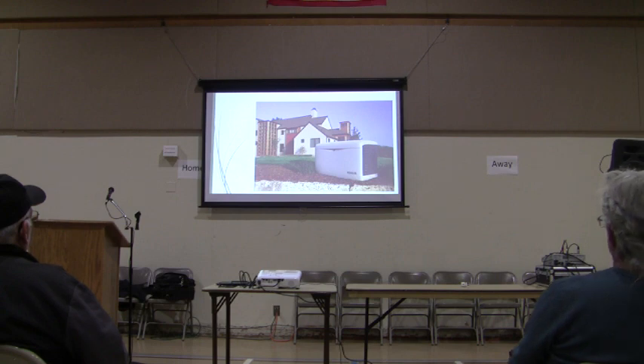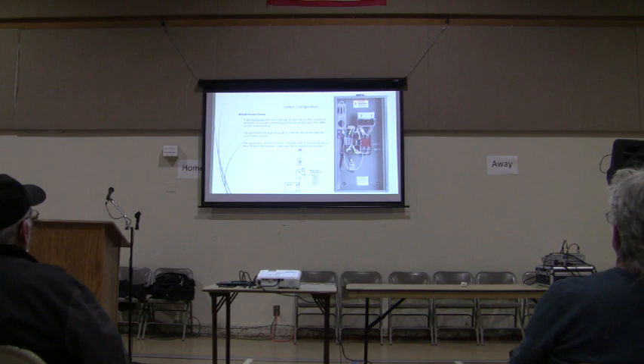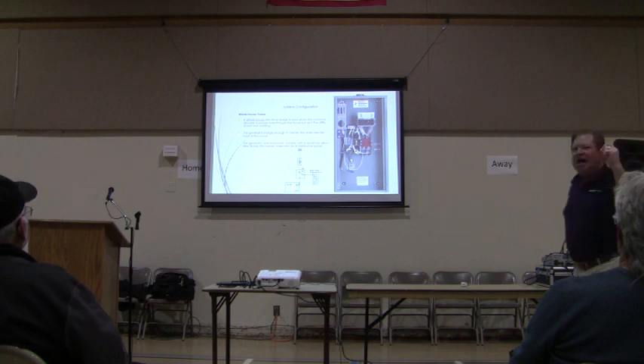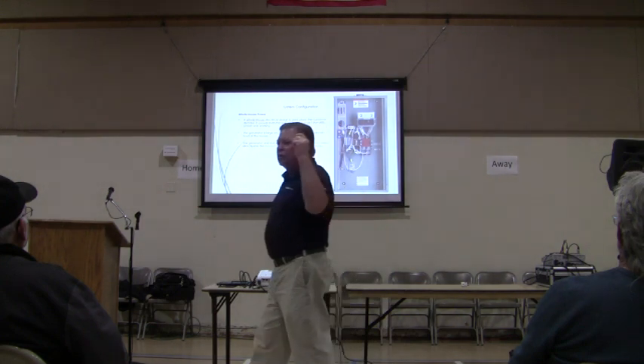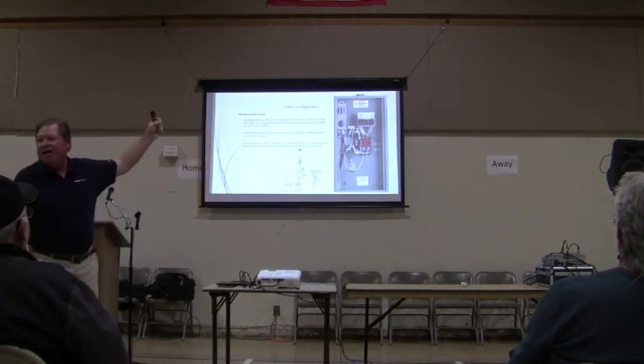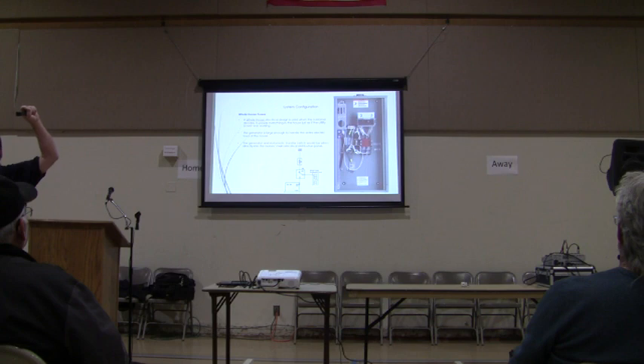A standby generator is going to look something like this. We're going to use a transfer switch that can be connected either to utility power or generator power, but not both simultaneously - and that's very important. I talked with an electrical supervisor today, and he made sure I would tell you: you cannot wire a generator into a circuit that can be fed by utility power at the same time.